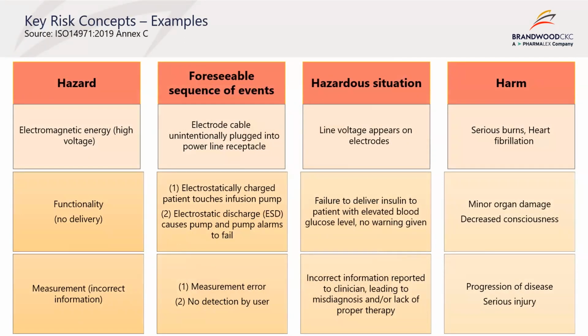To help better understand the concepts, this table lists some examples from Annex C of ISO 14971. The first example is an electrode hazard. The hazard here is electromagnetic energy, high voltage, for example. Foreseeable sequence of events is the electrode cable unintentionally plugged into power line receptacle. The hazardous situation is the line voltage appears on electrodes, and the harm are serious burns or heart fibrillation. The second example is for an infusion pump, where the functionality introduces a hazard, such as no delivery. There are two foreseeable sequence of events. Firstly, electrostatically charged patient touches infusion pump.